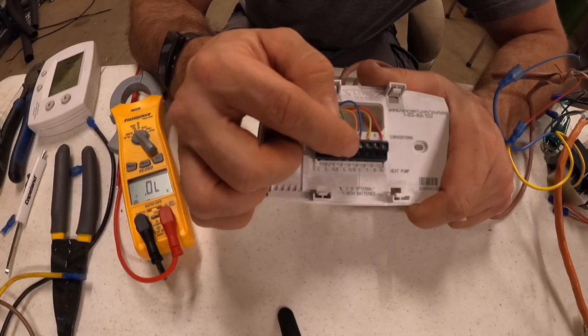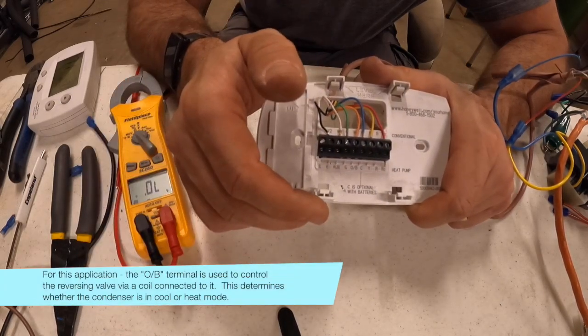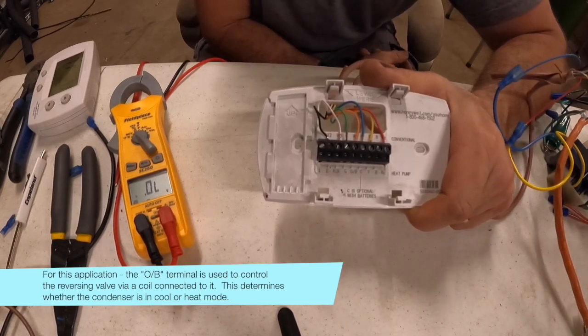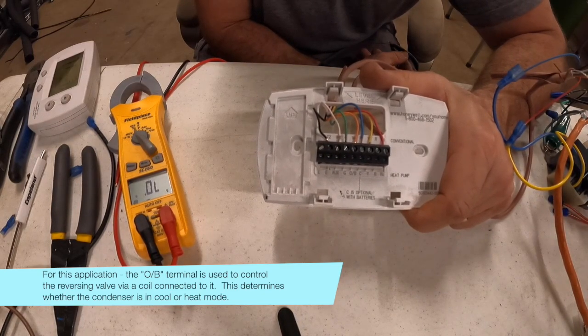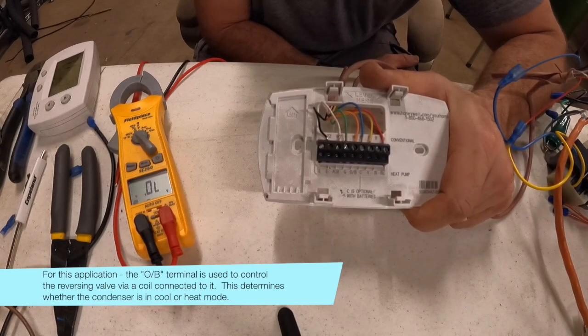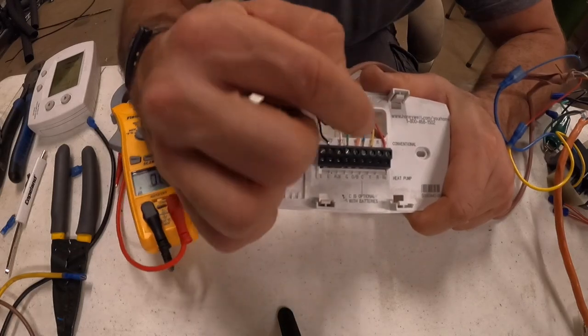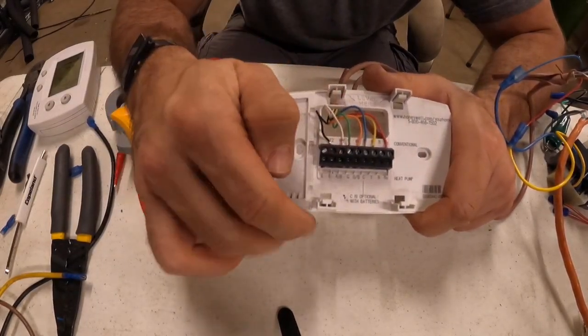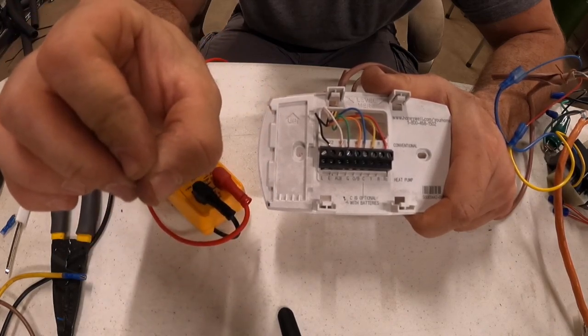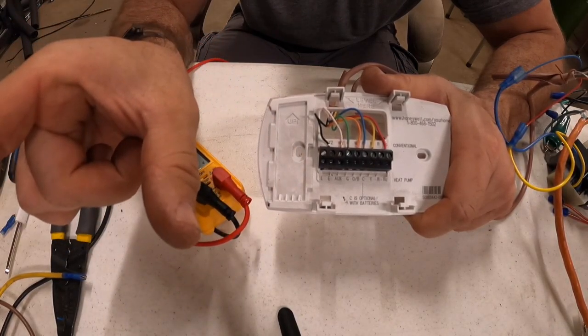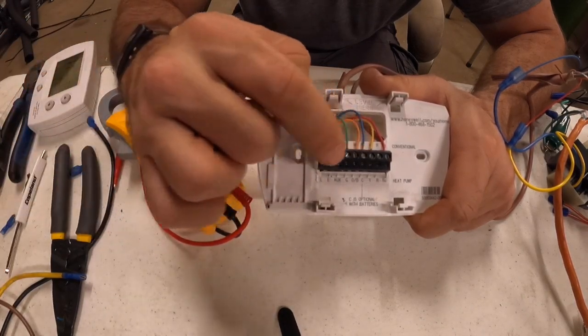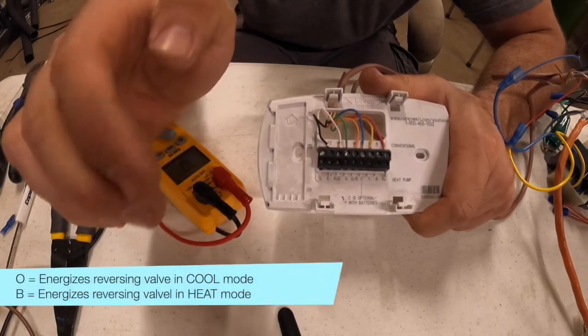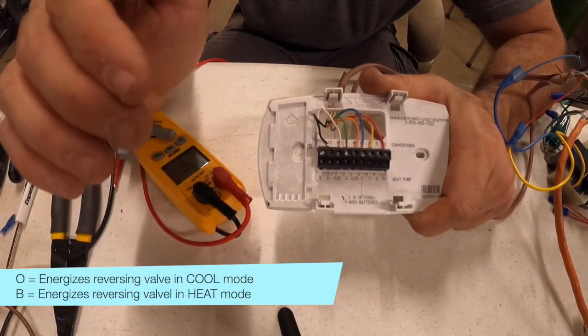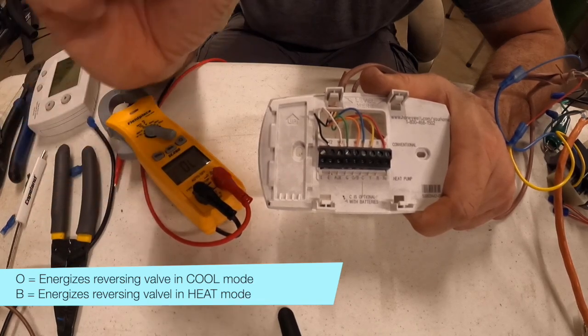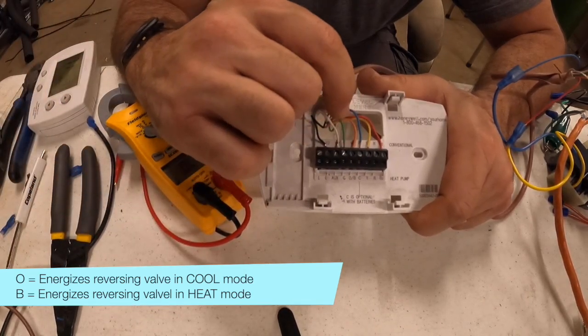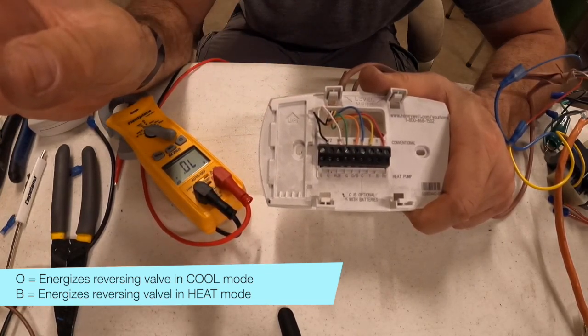All right, and then we've got OB here, which is the reversing valve. O is going to be for all units except for Rheem and Ruud. B is for Rheem and Ruud. So an O designation means that there is power supplied to the O terminal. We're using the orange wire here for systems where the reversing valve needs to be energized in cool mode. So that means when there's a call for cool on the thermostat, when you've set your thermostat lower than what the temperature actually is in the home and you have it set to cool and it turns the unit on, it's going to send voltage through this wire to engage the reversing valve.